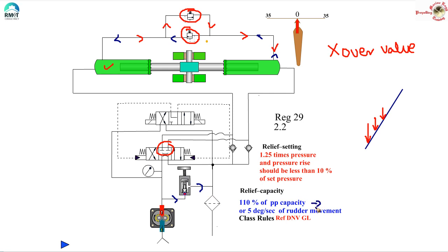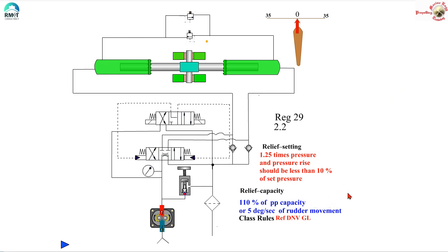The capacity of this relief valve should be 110% of the capacity of the pump — this figure comes from DNV class rules, not directly from SOLAS. SOLAS mentions 1.25 times the pressure setting and stops there, whereas figures like 10% accumulation and 110% pump capacity originate from class guidelines. There is another way to quantify the required capacity: the relief valve should also cater to 5 degrees per second of rudder movement.